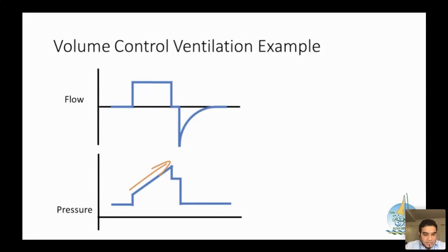During the inspiratory pause, I want you to correlate whatever you see down here to whatever you see in the flow chart up there. So now this is the end inspiratory pause. During the end inspiratory pause, this is where you should measure the plateau pressure. With expiration, there is a return to the set PEEP level. So if we're setting the PEEP to 5, you can see that the line is not going all the way down to 0, because we have already preset a PEEP of 5.